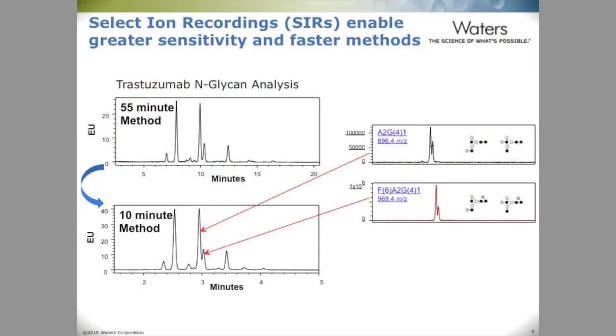The ACQUITY QDA enables a shorter chromatographic method through the ability to collect selected ion chromatograms or selected ion recording. You can look at the mass specifically of one particular glycan — or several glycans — and look at how they're changing differentially within the same process. The addition of mass information gives you the ability to target just those species of interest, so you don't need as much chromatographic resolution because you have the mass data.